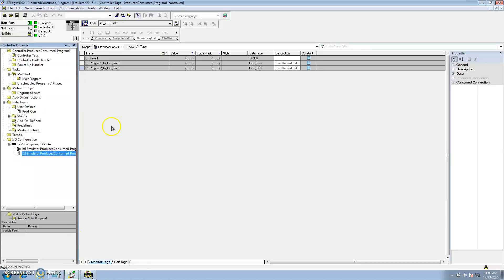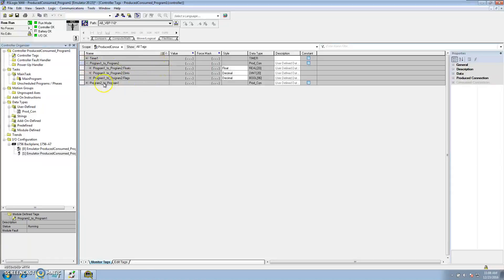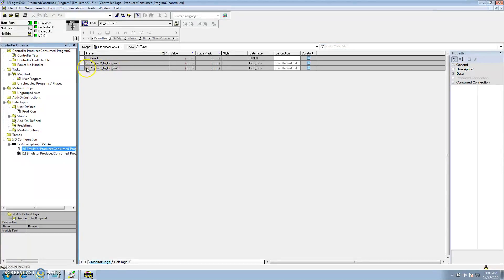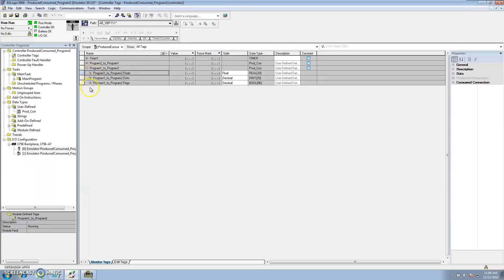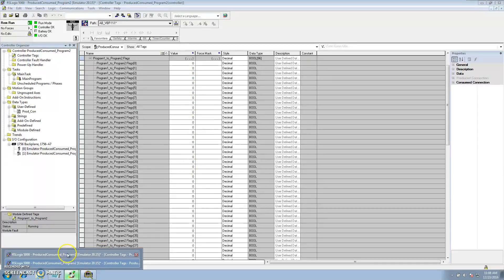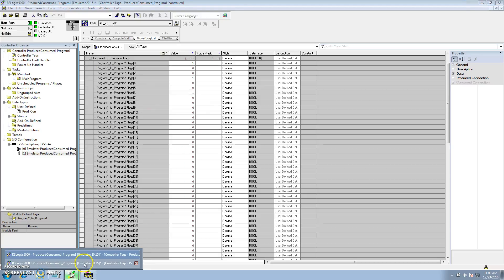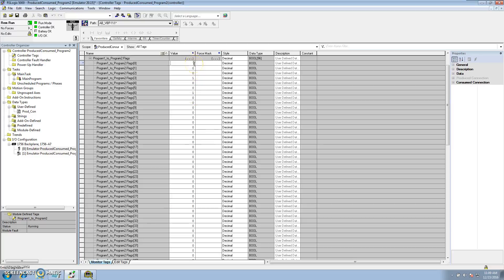To show that it works, go to Program One — this is the data going out to Program Two. We can select a flag, set it, then go to Program Two and check the same tag. You'll see all the same values there. Going back to Program One, since it's a Boolean I can only set a one or zero. The same data shows up in Program Two. I can't write over it in Program Two because it's being written by Program One — that data is constantly being controlled from the other processor.